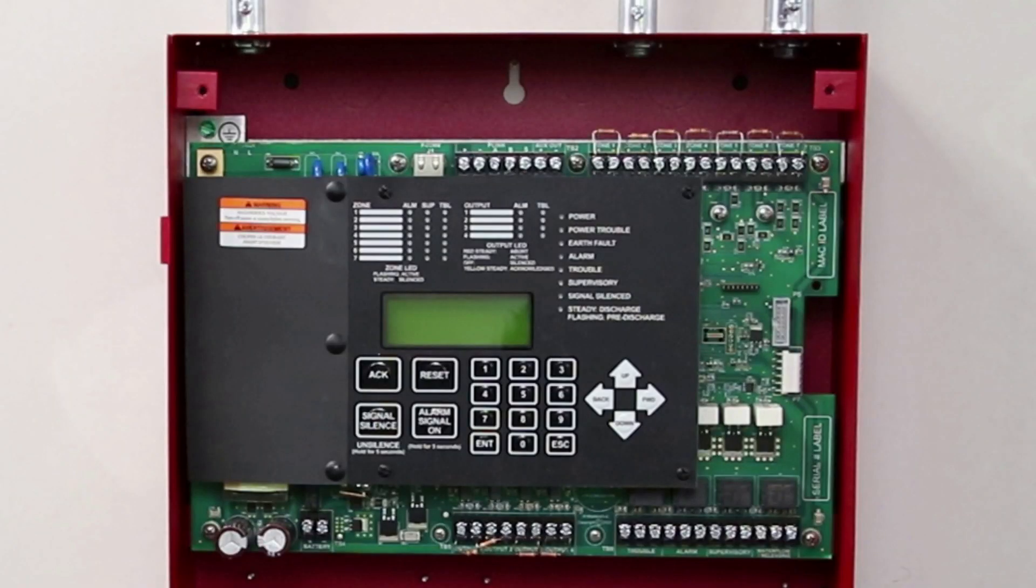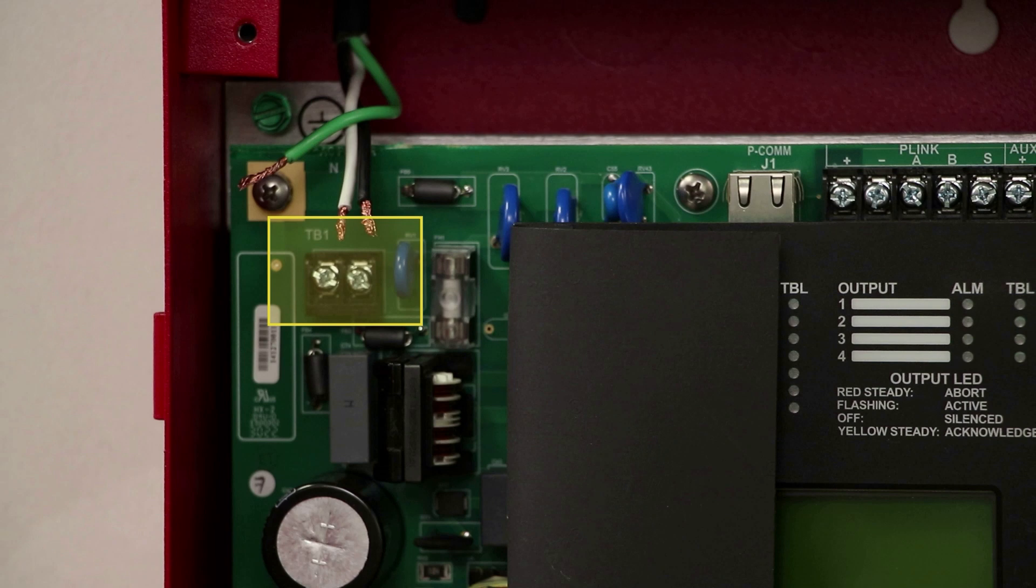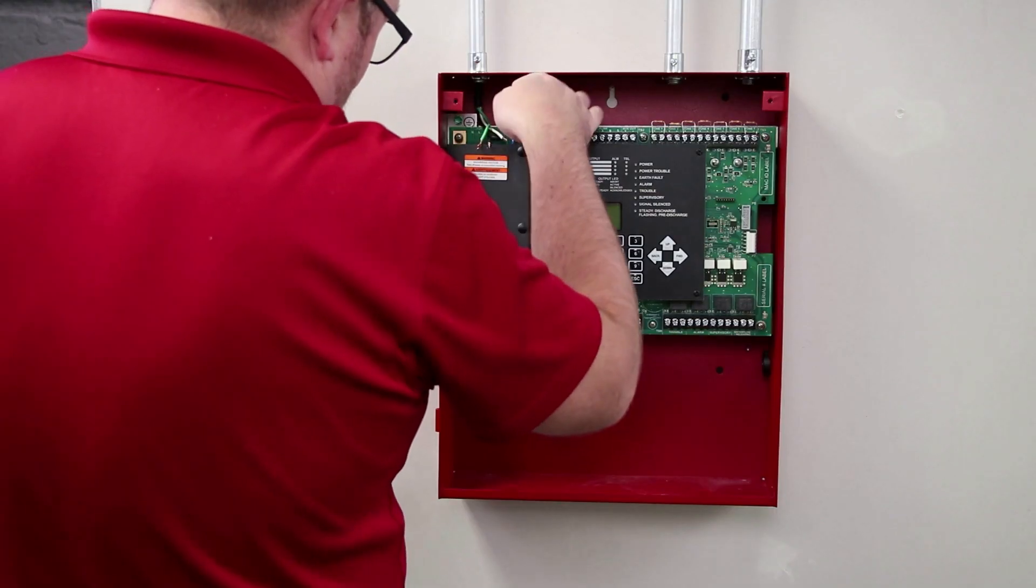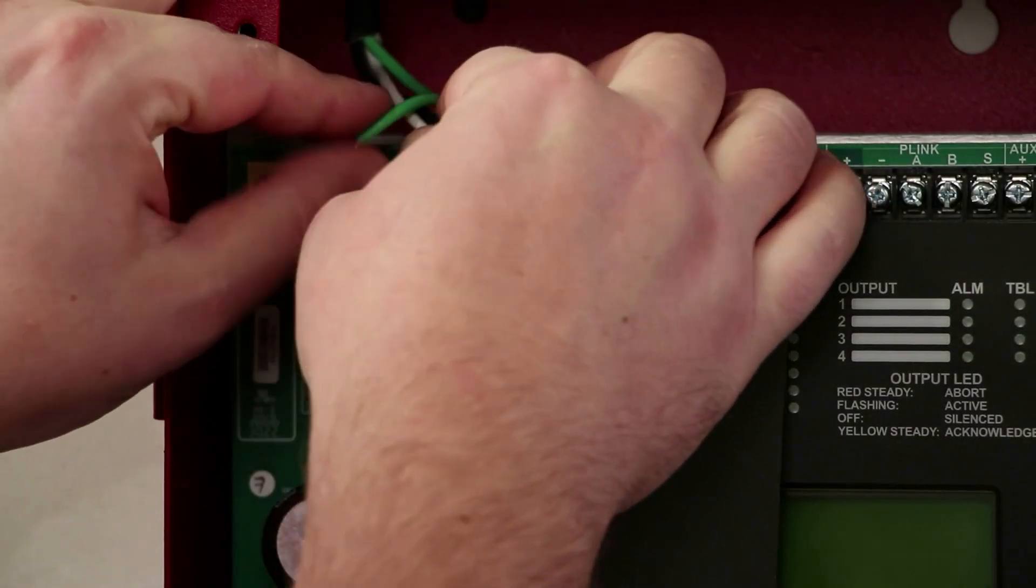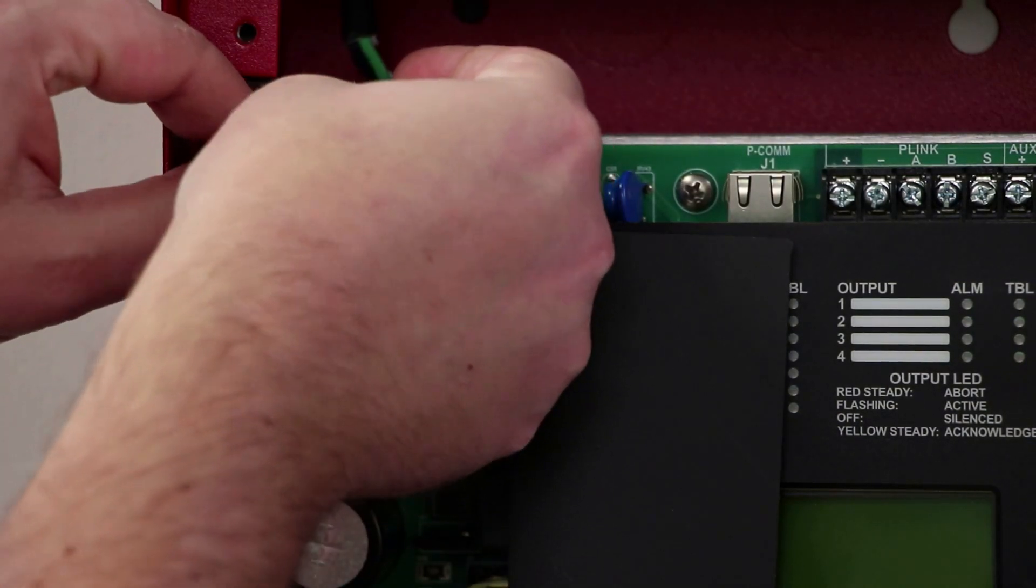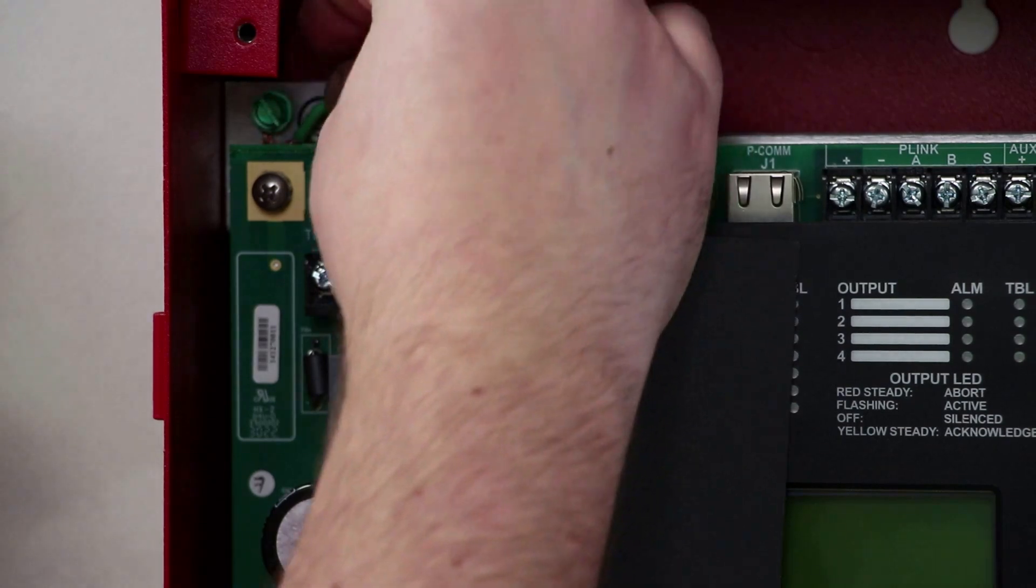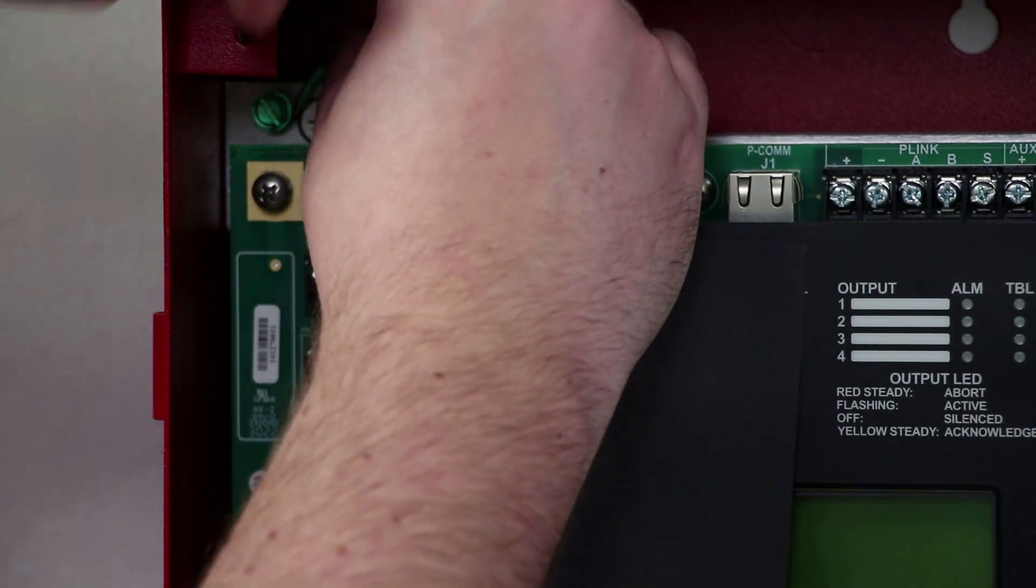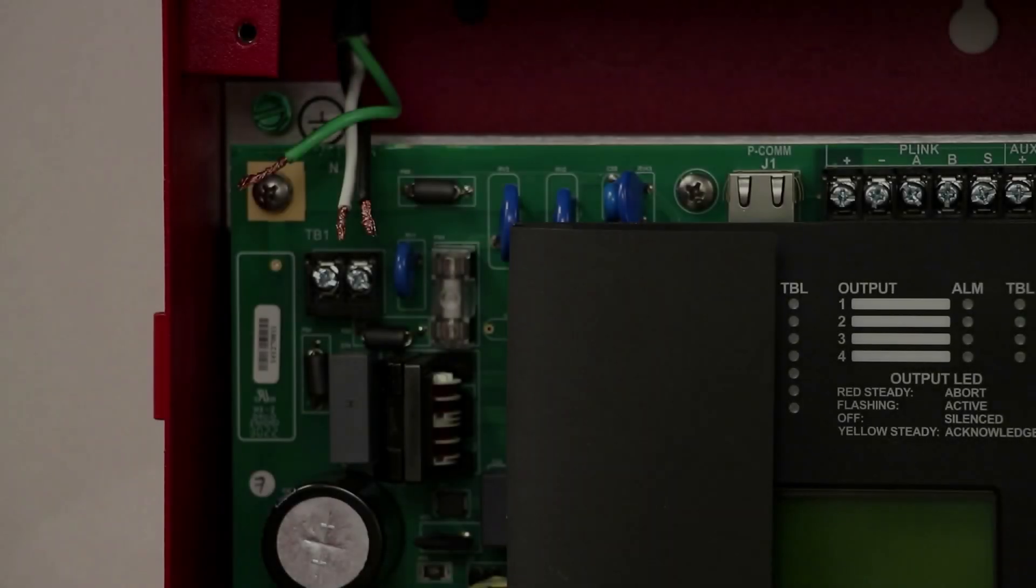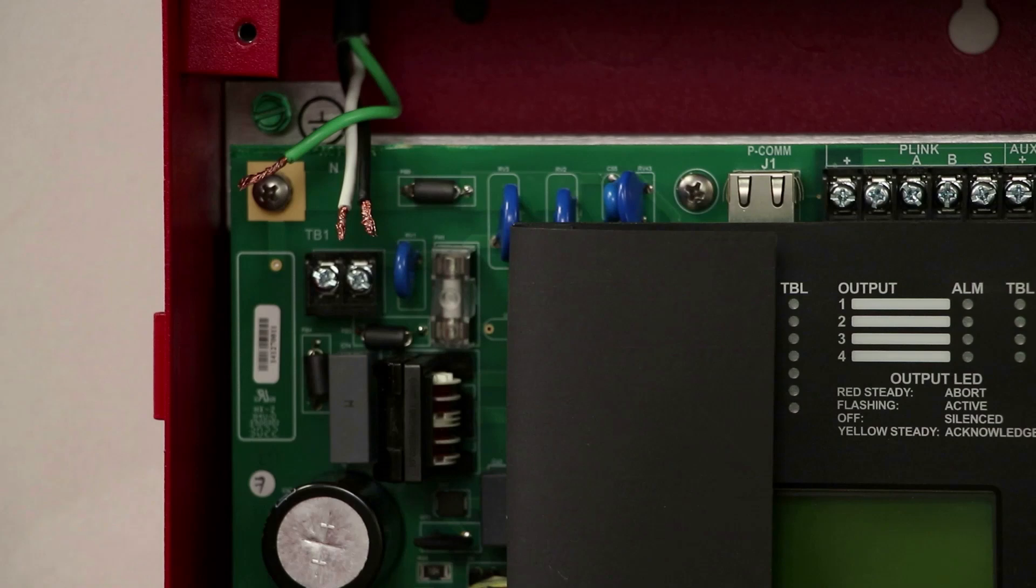The panel is auto sensing for 120 or 240 volt AC at either 50 or 60 Hertz. The AC terminals are located in the upper left hand portion of the main board and are labeled AC power. With the AC power still turned off at the circuit breaker, make the AC connections at the panel. The earth ground connection is located on the mounting rail. The line and neutral connections are located on TB1. Fold the insulation protecting TB1 to the side to gain access.